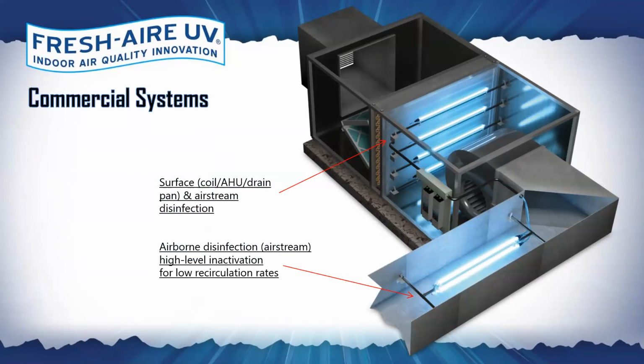But the real advantageous strategy for a facility like that is putting the UV lights in the air handling section. Enjoy all those benefits by having a cleaner, sterile coil, not having the coil be a source of biological fouling and contaminants. Keep it clean and continually disinfect the air as the air passes through the air handling unit. Now, if this was before COVID, typically, if we're doing coil disinfection, it'd be 1 lamp every 30 or 40 inches. In this example, you see there's 4 lamps. So what we do now, for those coil mount applications that want a higher level of airstream disinfection, is put 1 lamp every 10 to 15 inches. So we will put in more lamps to compensate for the fact that the air is moving perpendicular over the lamp, right? We're not getting the same dwell time as a duct mount, but with enough UV, we are able to achieve the same neutralization.